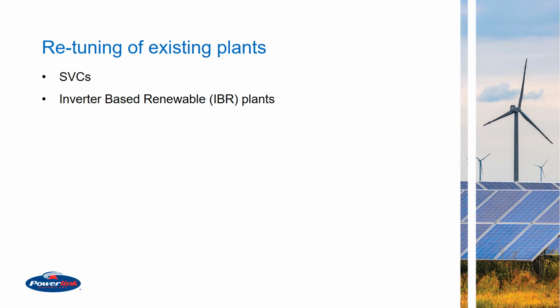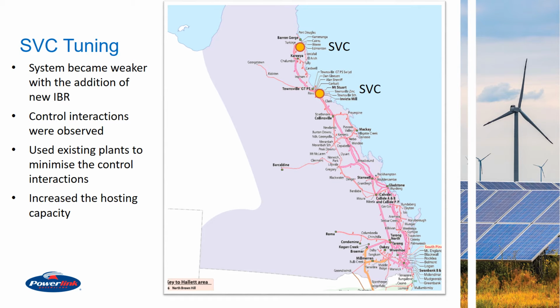So what we have done in Queensland, we have used our SVCs and existing renewable plant to minimize those control interactions, or in other words, to increase the system strength without actually adding fault level to the system. So in the first example, I'll be talking about SVC tuning. As you can see, there are two existing SVCs, one in Townsville area and one in Warri region.